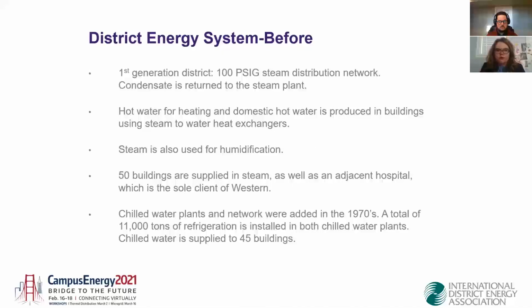Steam is used for humidification, and 50 buildings are supplied by steam. There's a hospital as well on the campus, and it's the sole external client of Western. All the other buildings supplied by the energy are Western owned. The chilled water plants were added later on, in the 1970s, and there's a total of 11,000 tons of refrigeration installed in both plants together.